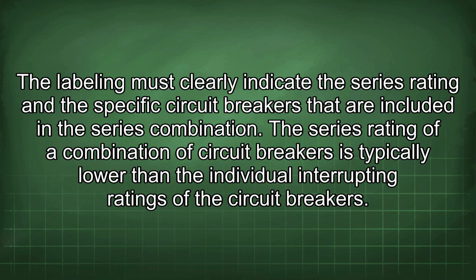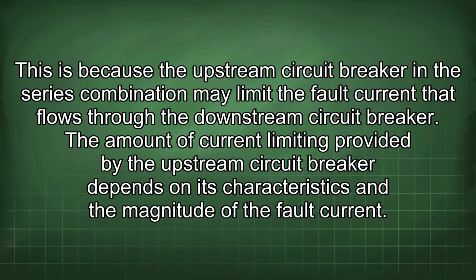The series rating of a combination of circuit breakers is typically lower than the individual interrupting ratings of the circuit breakers. This is because the upstream circuit breaker in the series combination may limit the fault current that flows through the downstream circuit breaker. The amount of current limiting provided by the upstream circuit breaker depends on its characteristics and the magnitude of the fault current.